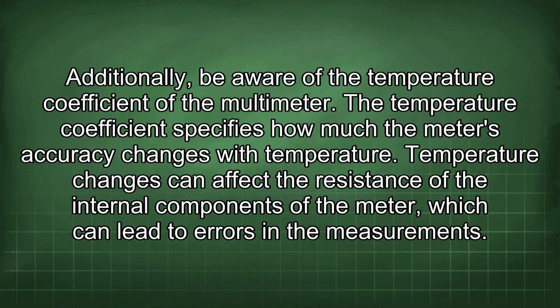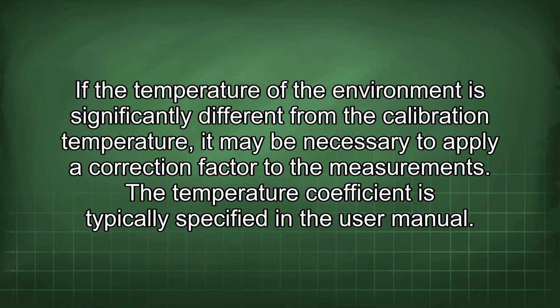Additionally, be aware of the temperature coefficient of the multimeter. The temperature coefficient specifies how much the meter's accuracy changes with temperature. Temperature changes can affect the resistance of the internal components of the meter, which can lead to errors in the measurements. If the temperature of the environment is significantly different from the calibration temperature, it may be necessary to apply a correction factor to the measurements. The temperature coefficient is typically specified in the user manual.